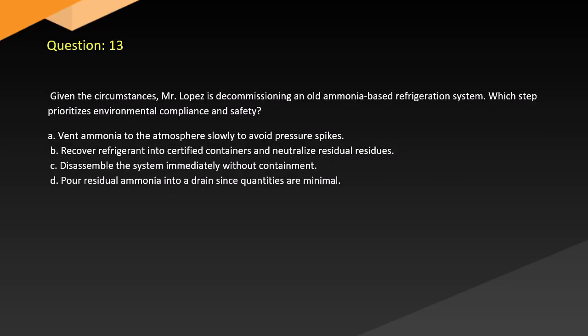Question 13. Given the circumstances, Mr. Lopez is decommissioning an old ammonia-based refrigeration system. Which step prioritizes environmental compliance and safety? A. Vent ammonia to the atmosphere slowly to avoid pressure spikes. B. Recover refrigerant into certified containers and neutralize residual residues. C. Disassemble the system immediately without containment. D. Pour residual ammonia into a drain since quantities are minimal.